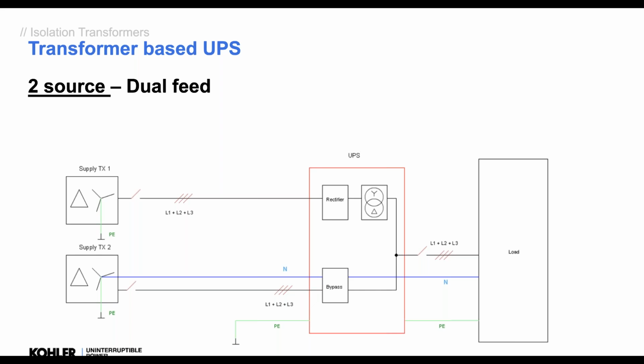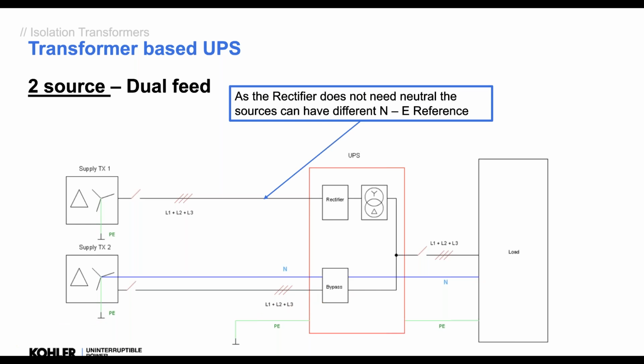So for dual feed with an old type of UPS, we have a supply transformer, PES here, three-wire to the rectifier, no problem. The PES on supply 2 on the bypass supplies the neutral for the UPS, for the load, for the bypass, and it goes out that way. Okay. So we're not connecting different neutrals together in a traditional way. Okay, and many UPSs fitted many years ago were like this.